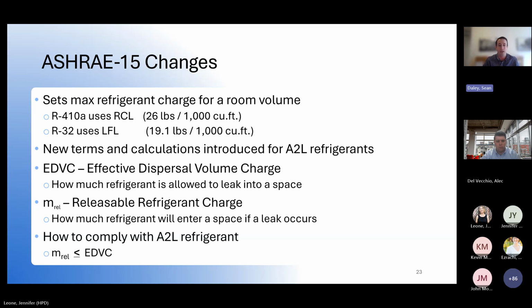So in general, how do we comply with ASHRAE 15 with A2L refrigerants? We have to make sure our releasable charge is less than or equal to our EDVC, which is the max charge that can leak into that space from a safety perspective. Next slide, please, Jennifer.